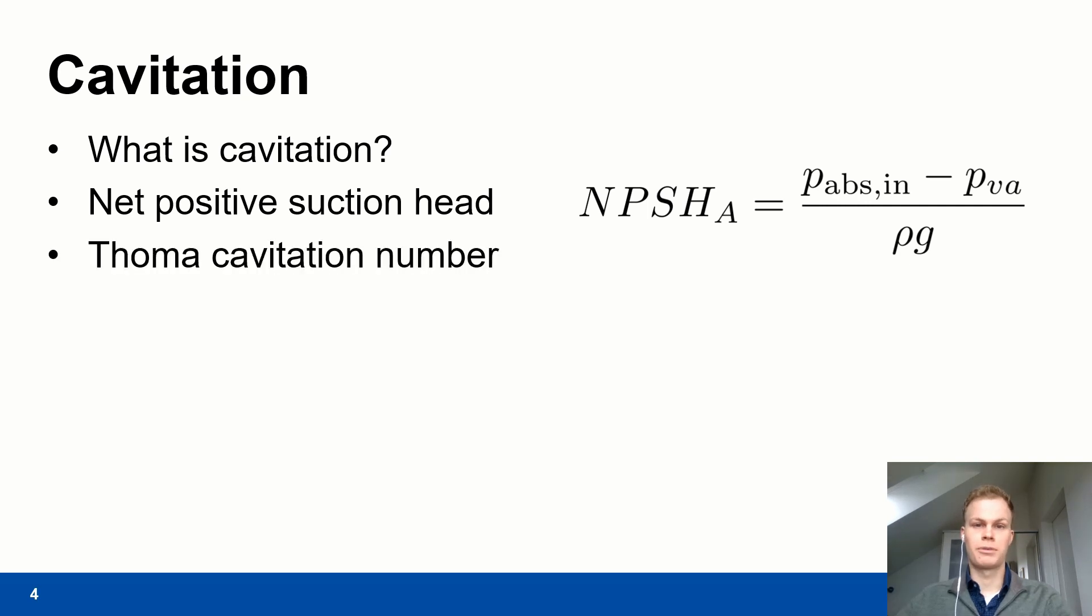The Thoma cavitation number is a dimensionless term indicating about the same as the net positive suction head and it is defined as the available net positive suction head divided by the head of the turbine.